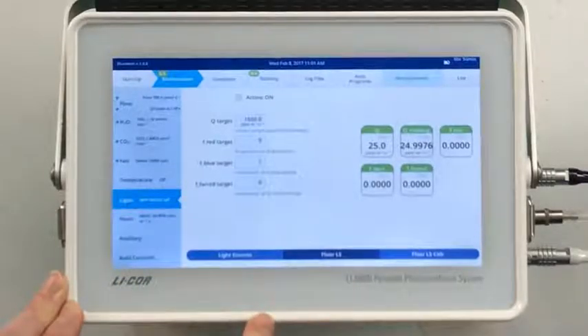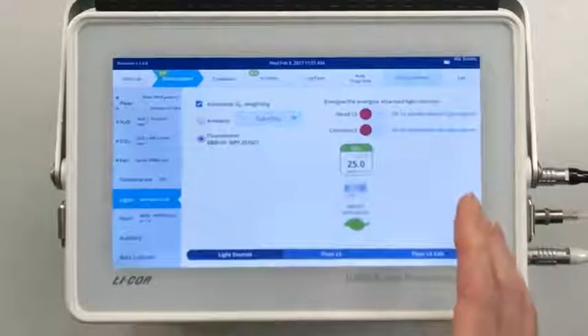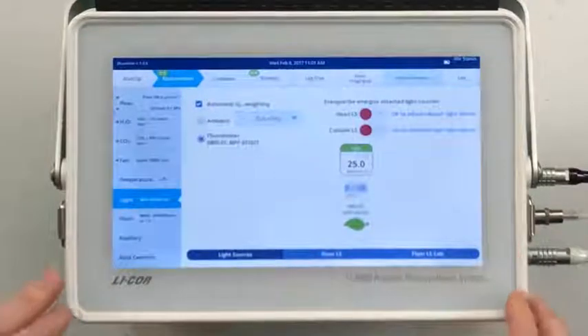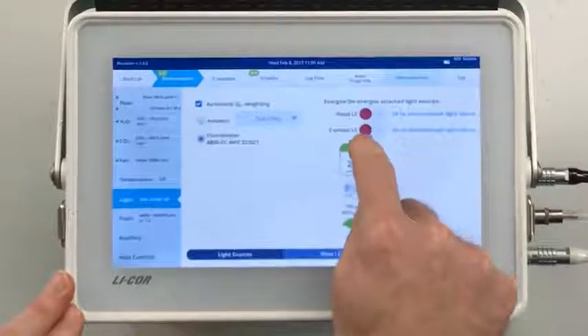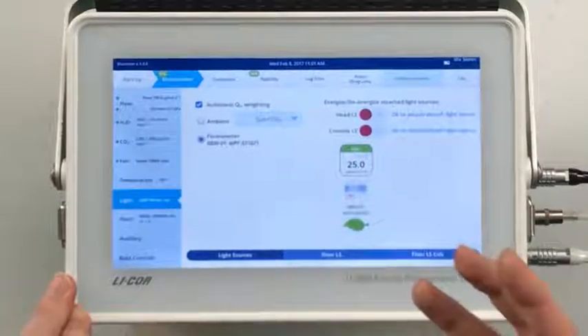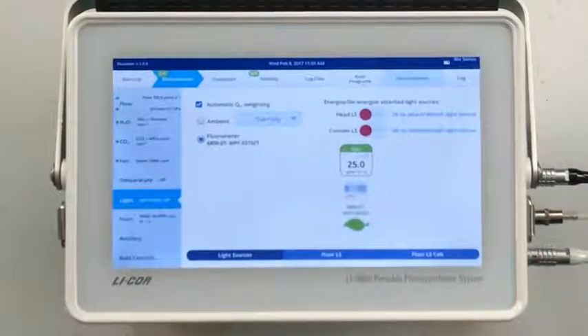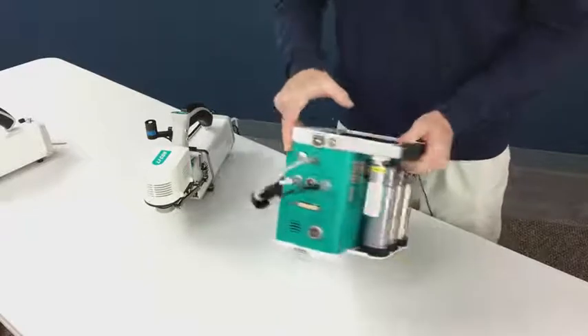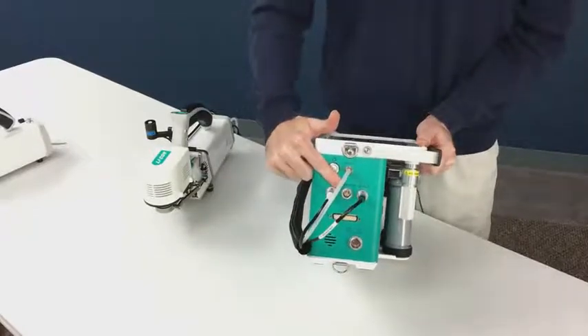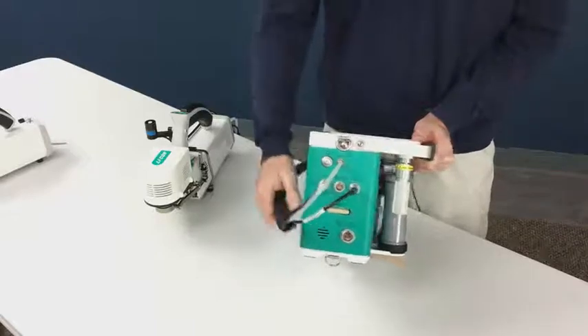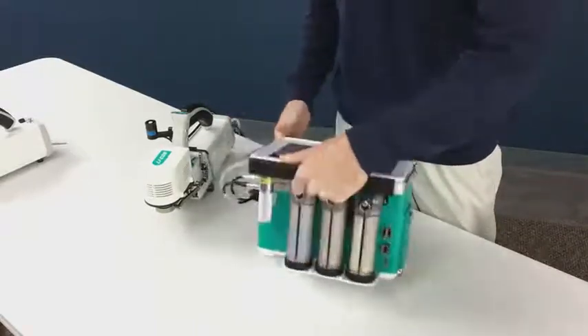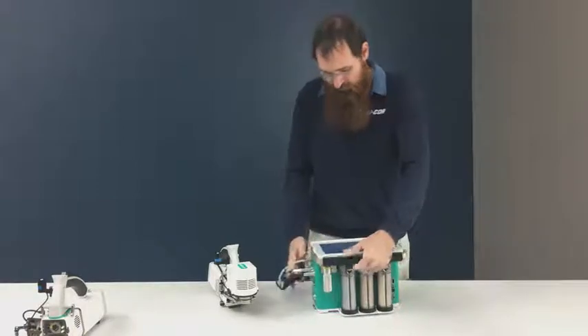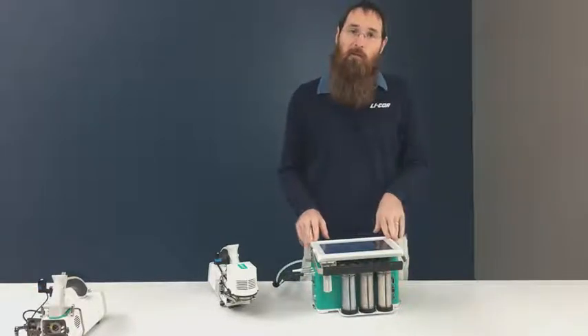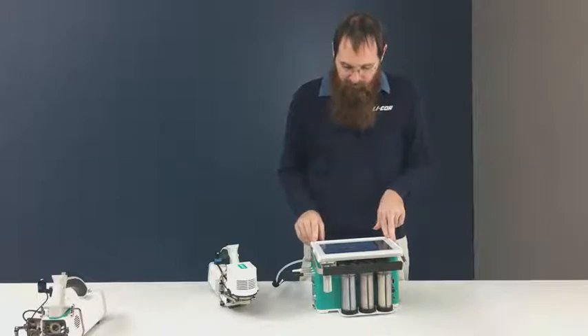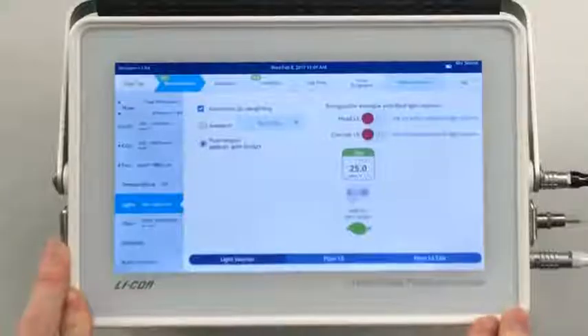Okay? For light, the light source lets us pick the source that's connected to the instrument. You'll note here that it says head light source, console light source. When I flip the chamber over, I showed you one light source connector. On the side of the console, we have another connector called accessory. And at some point in the future, it's quite likely you will be able to plug a light source in here, right? Software is set up for it, hardware is set up for it. We don't have a cable currently, right? So I can pick what light source I'm operating and where it's at.